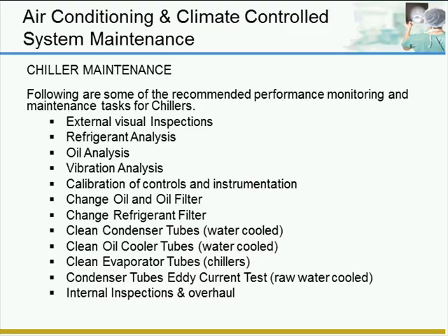You look at your compressor journal and thrust bearings, the drive gears, the seals, and always the safety relief or the rupture disc. You never want the system to overpressurize. Different equipment requires different service.